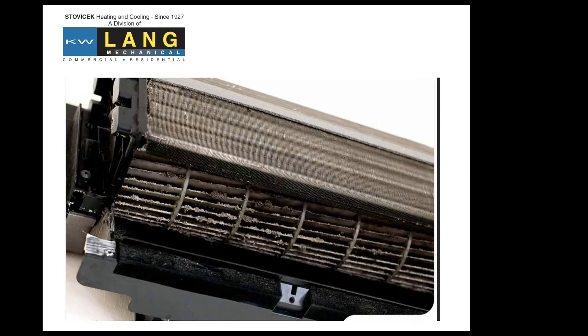This is a mini split inside head system that was in a server room. They called and said we hadn't been out there in probably four or five years and the unit just quit cooling. We got there, took the cover off, and it was pretty built up with dirt and mold. The drain pan had been dripping, and we ended up just removing it off the wall and replacing the head assembly because there was just no way to really clean it. Just preventative maintenance — we hadn't seen this person in about five years.